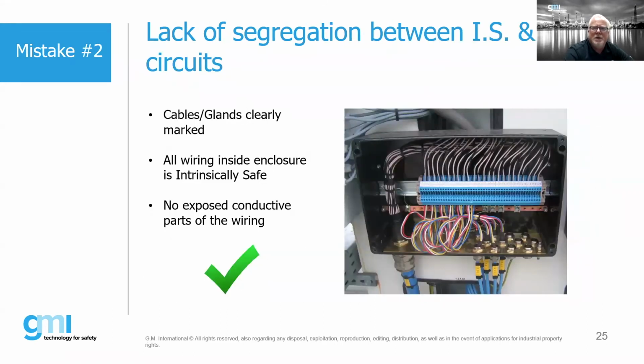The second one is the segregation between intrinsically safe and non-intrinsically safe circuits. In this enclosure, what you're seeing is that we have our glands, or at least we have our cabling marked. We certainly have some loops going in. In this case, we have an enclosure strictly with intrinsically safe terminals, so everything looks fine. There's no conductive parts of the wiring that are shown.